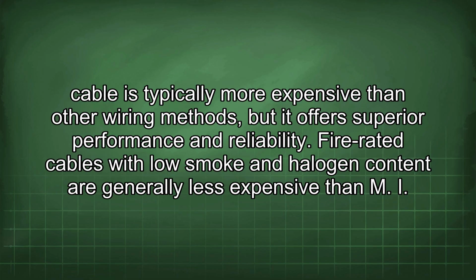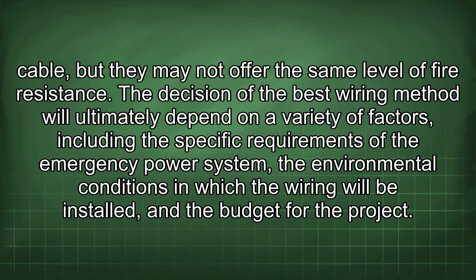Cable is typically more expensive than other wiring methods, but it offers superior performance and reliability. Fire-rated cables with low smoke and halogen content are generally less expensive than M.I., but they may not offer the same level of fire resistance. The decision of the best wiring method will ultimately depend on a variety of factors, including the specific requirements of the emergency power system, the environmental conditions in which the wiring will be installed, and the budget for the project.